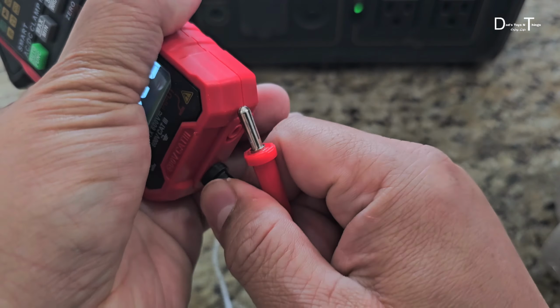I'm reading 2.5, so let's hold that — 2.77. Now according to the manufacturer, this should be about 0.5 to 1. What I'm going to do now is switch from auto to the actual current measurement mode and hold that. Okay, now it's in manual, set to current, and I'll measure it once more. Now I'm getting about 0.92, which is well within the specification of the inverter.